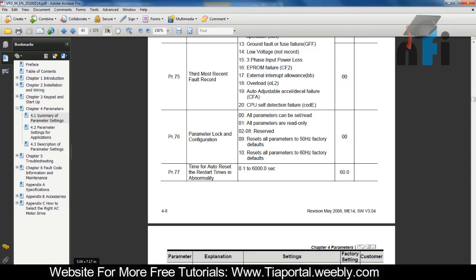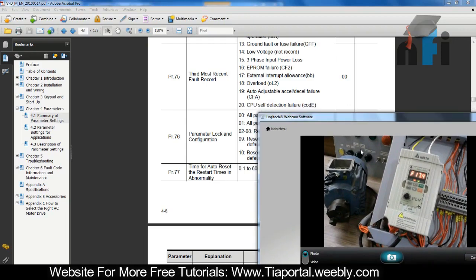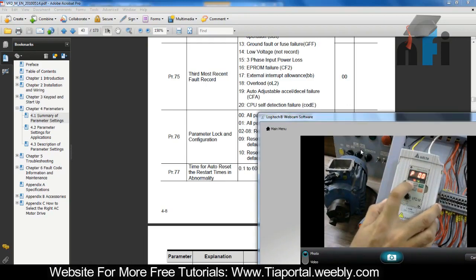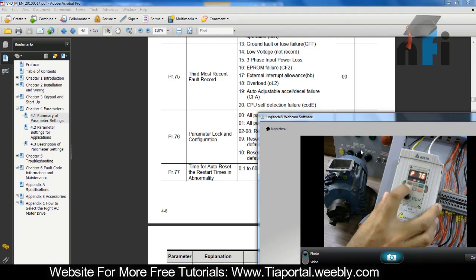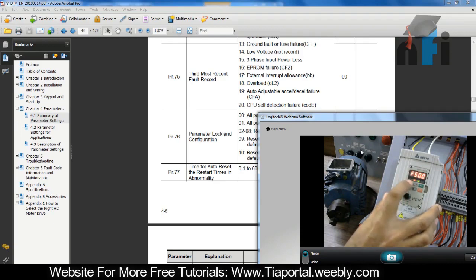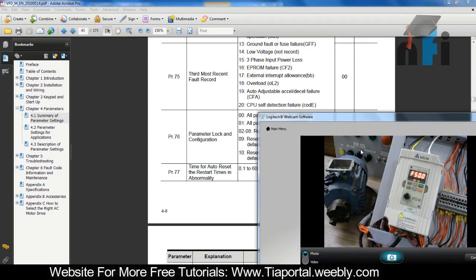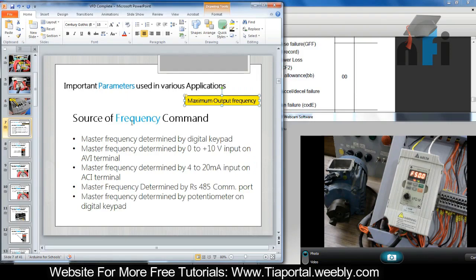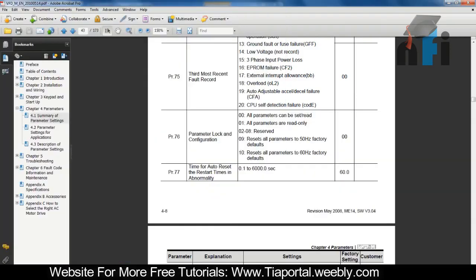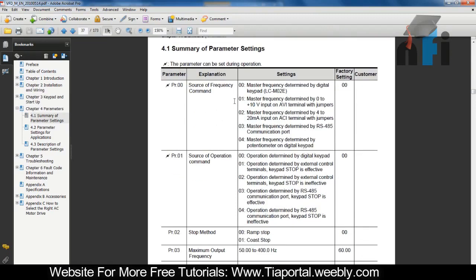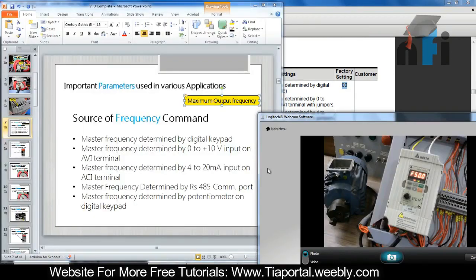So on this drive, I'm going to navigate to parameter 76 by pressing MODE once. I'll increment to 76, then press ENTER, go to 9, and press ENTER. Now that's reset to factory defaults. Going back to frequency, let's move to the first parameter - Source of Frequency - which is parameter 00. Source of frequency 00 means master frequency is determined by the digital keypad. Factory setting is 00, so by default it's 00.